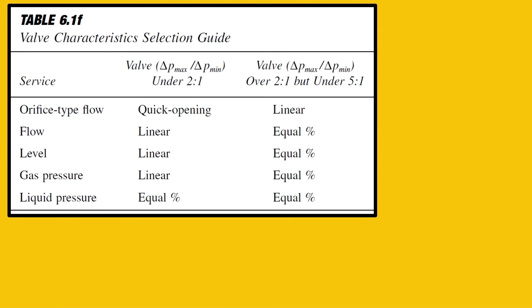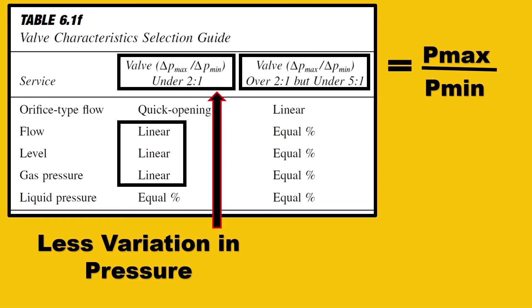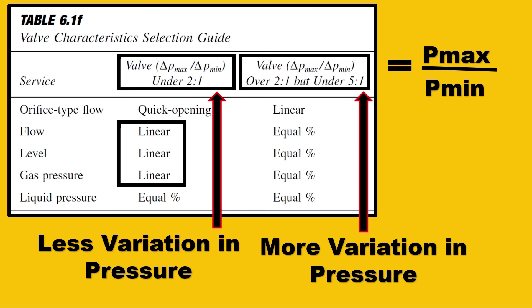The basic concept is: if the pressure variation (Pmax/Pmin) is less, you have less deviation from the characteristics, so you can go for linear characteristics. But if the pressure variation is more, you should go for a characteristic that can balance it. Usually, you go for equal percentage, with the final balanced value being linear characteristics.